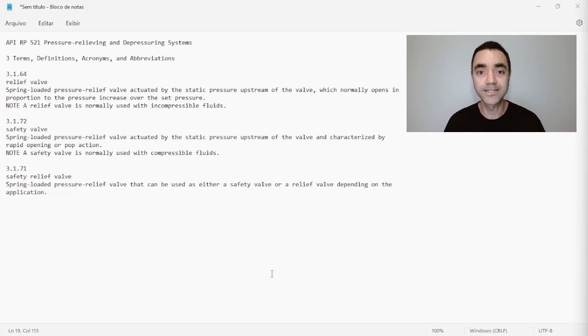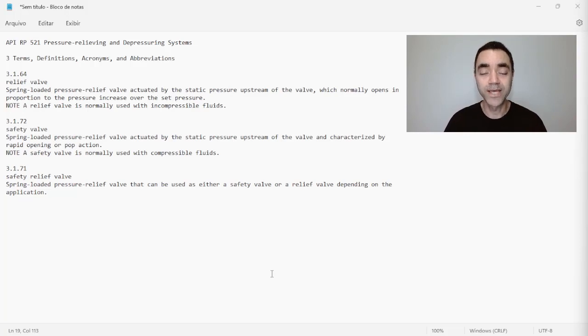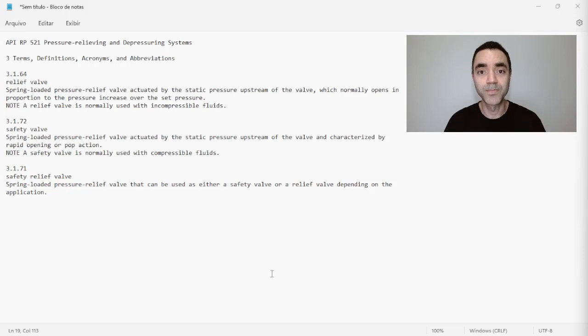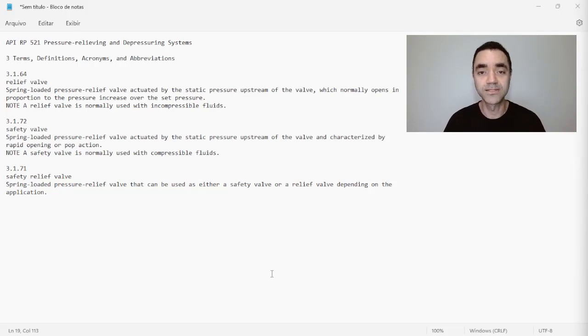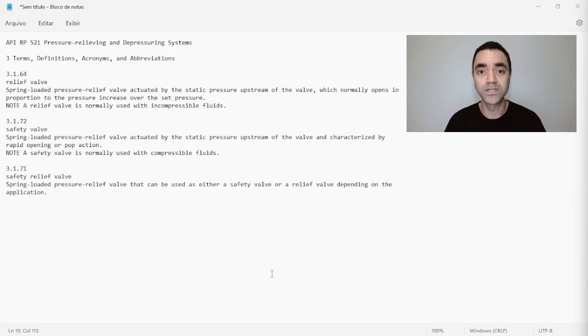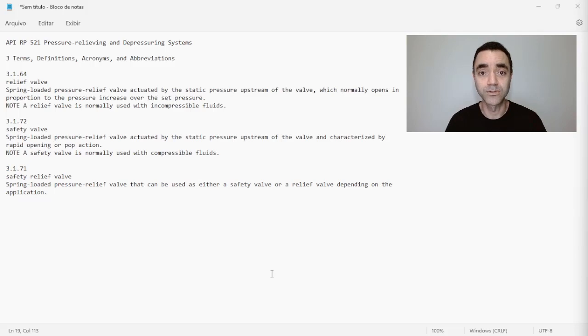So safety valve is normally used with compressible fluids. So you can see that the action, the way that both are actuated, is the same. But what differentiates both of them, relief valve and safety valve, is mainly the fluid—what kind of fluid is being handled by this pressure safety device: is it compressible fluid or incompressible fluid?